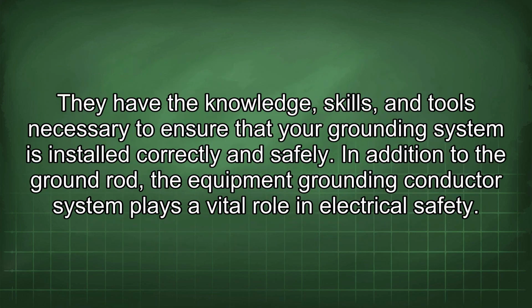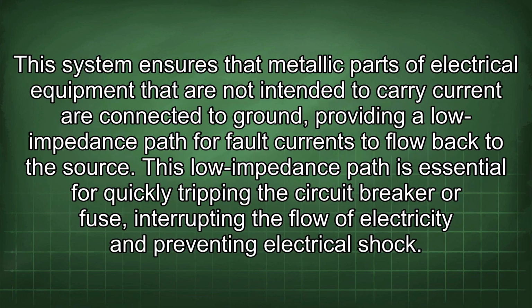They have the knowledge, skills, and tools necessary to ensure that your grounding system is installed correctly and safely. In addition to the ground rod, the equipment grounding conductor system plays a vital role in electrical safety. This system ensures that metallic parts of electrical equipment that are not intended to carry current are connected to ground, providing a low impedance path for fault currents to flow back to the source.